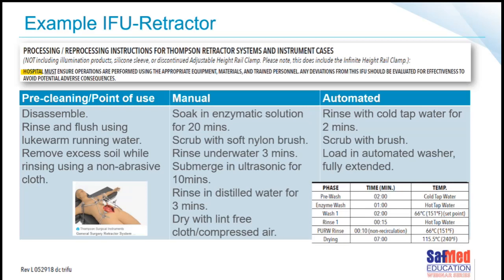Okay. Now, if you've got a washer, you would have done the pre-cleaning part first, and you would have skipped that manual section. But before you put it in the washer, the instructions will say, rinse with cold tap water for 2 minutes. Scrub with a brush. Load in the automated washer, fully extended. Then it goes on to describe the phases and the cycles, the wash cycles in the machine itself. So you can't just choose any old cycle parameters, and you can't just press, okay, I'll just do the one with the one wash, the quick wash.